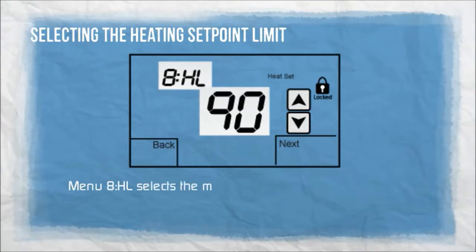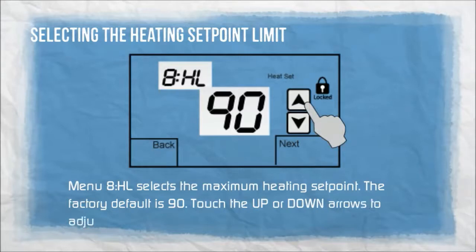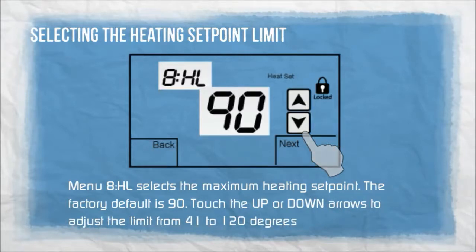Menu 8HL selects the maximum heating set point. The factory default is 90. Touch the up or down arrows to adjust the limit from 41 to 120 degrees Fahrenheit.